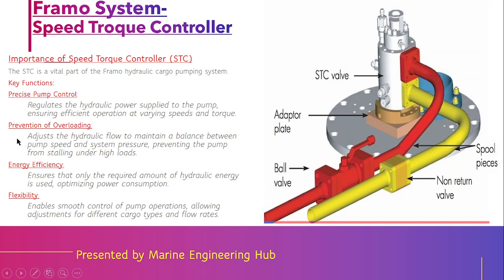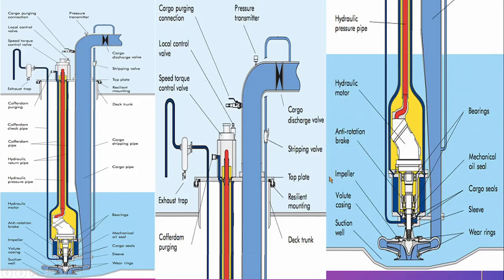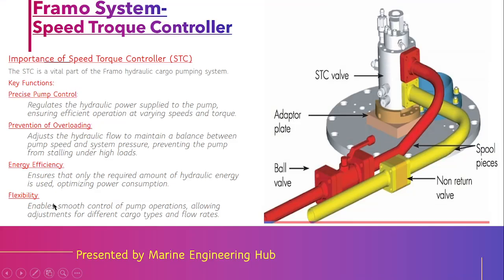The speed torque controller helps with precise pump control — it varies the speed and torque of the pump by varying the amount of oil flowing to the hydraulic motor. It also helps in prevention of overloading: it flows only the amount of oil sufficient to balance the pump and system pressure, preventing the system from stalling. It also helps in optimization of power consumption — for example, if we want to develop 5 bar from a centrifugal pump, the controller regulates the hydraulic oil flow so the motor runs at exactly the right speed.